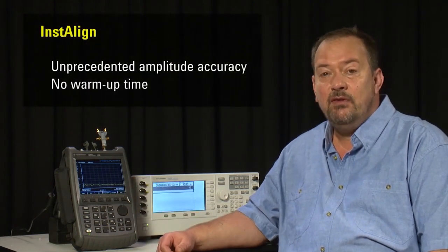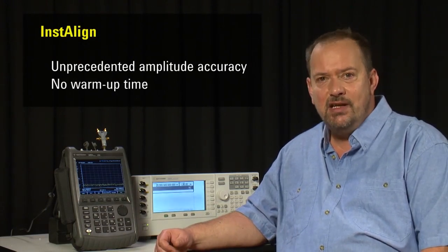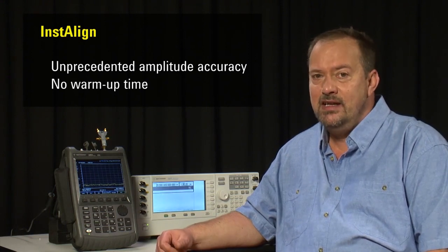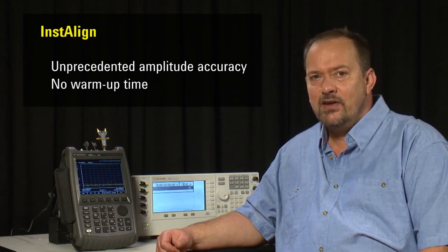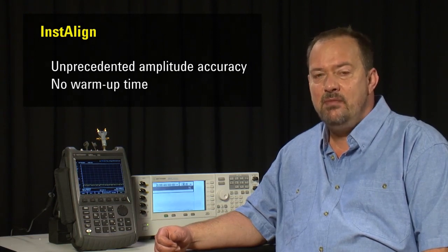Agilent's InstAlign technology performs a realignment before every sweep. This results in extremely high amplitude accuracy at all times, regardless of ambient temperature and regardless of how long it's been turned on. As a result, the FieldFox has a zero warm-up time, so it's always in spec from the moment you switch it on.